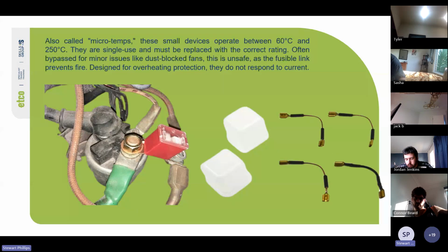Also called micro temps, these small devices operate between 60 degrees and 250 degrees C. They are single use and must be replaced with the correct rating. Often bypassed for minor issues like dust blocked fans. This is unsafe as a fusible link prevents fire. Designed for overheating protection, they do not respond to current.